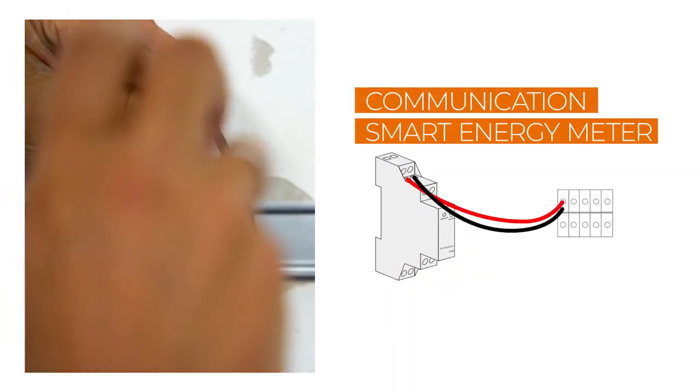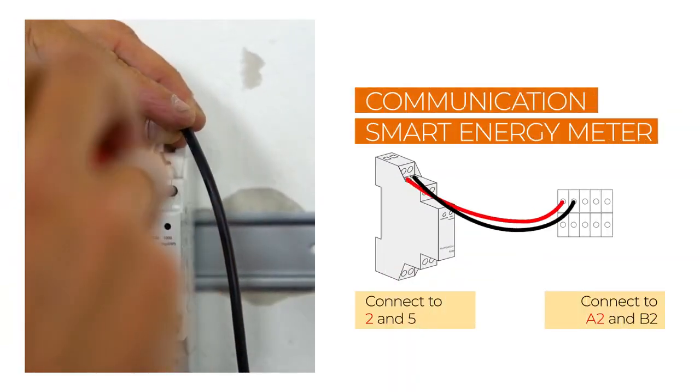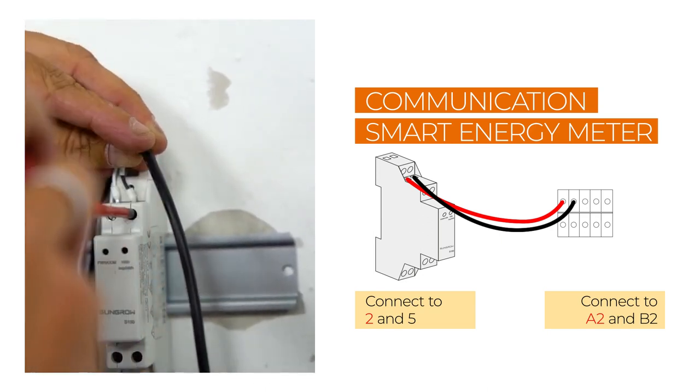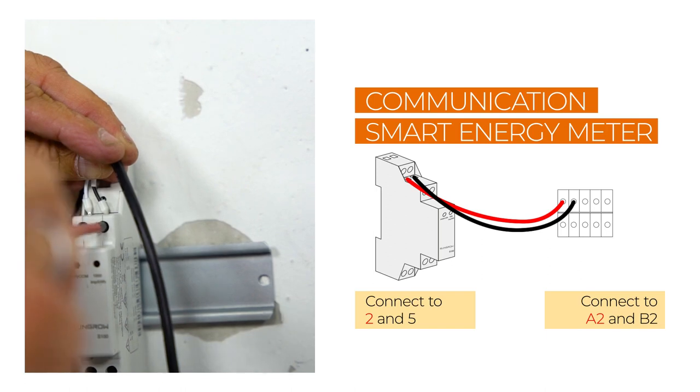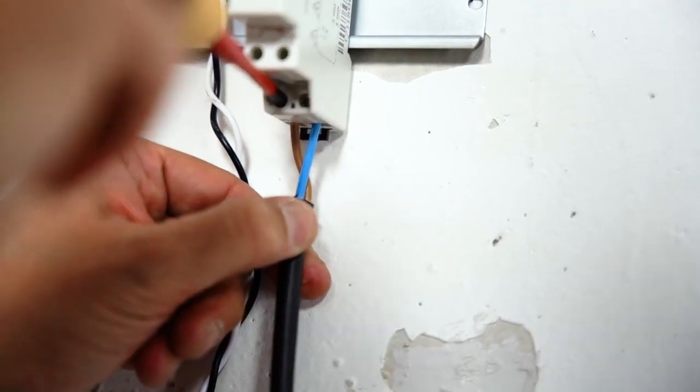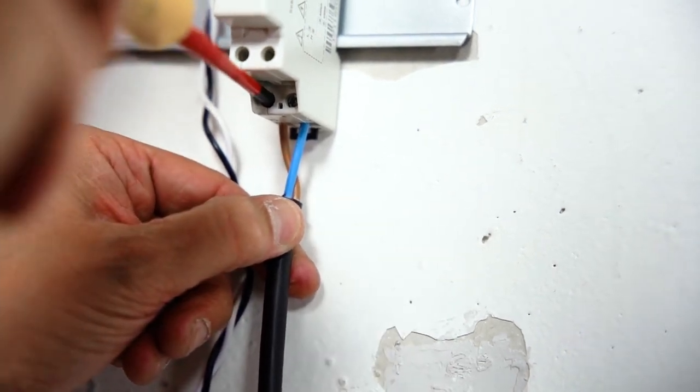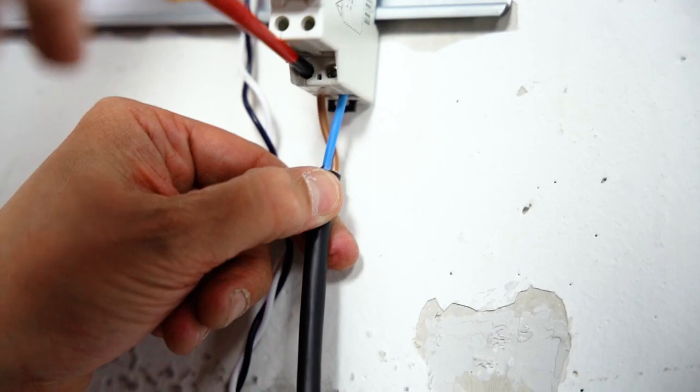Now let's connect the smart energy meter itself. Mount the meter on a DIN rail and connect the communication cable RS-485A to pin 2 and RS-485B to pin 5 on the meter. The meter must be supplied with 230 volts. Connect the line cable to pin 3 and the neutral cable to pin 6.